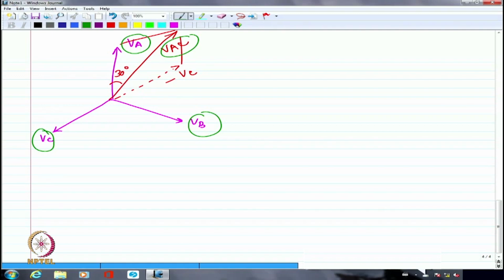I can say 30 degree lead or 30 degree lag depending upon which line voltages I am looking at. For example, VAC is giving 30 degree lag compared to VA. Whereas if I am looking at VAB, that will have a 30 degree lead. So in general, a 30 degree phase shift comes out between the primary line voltage and the secondary line voltage whenever I have either star-delta or delta-star configuration.